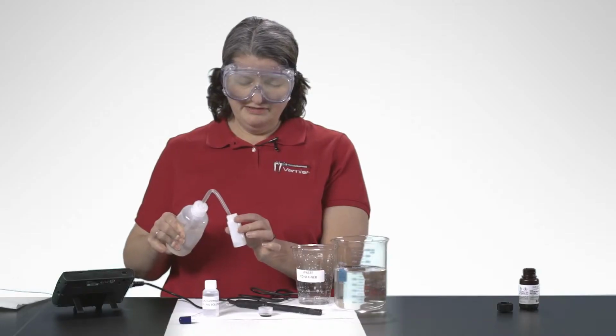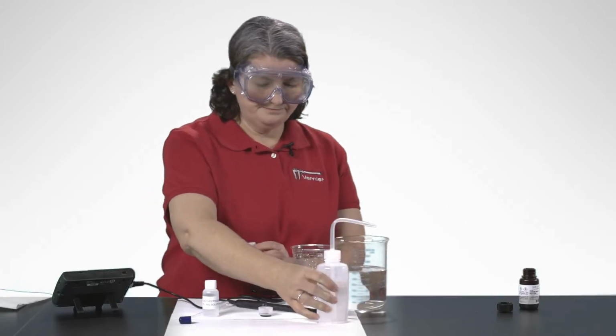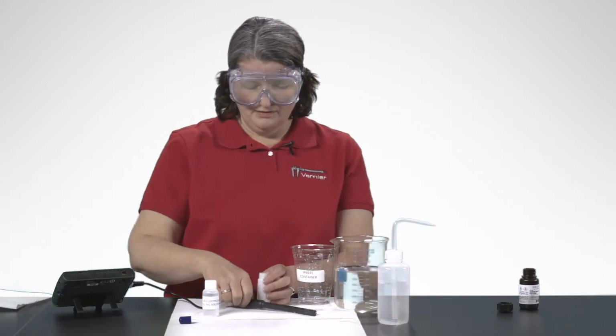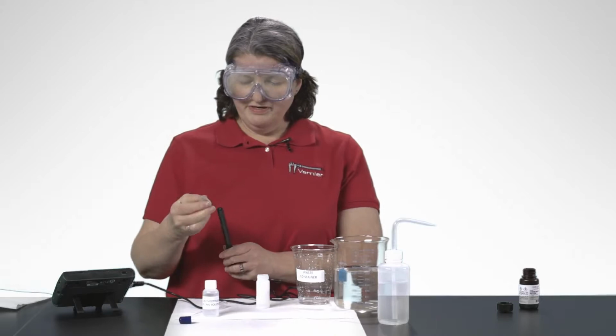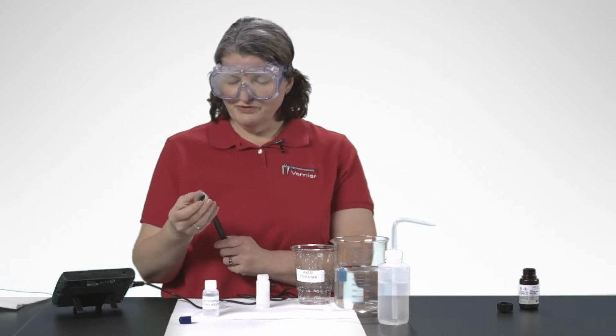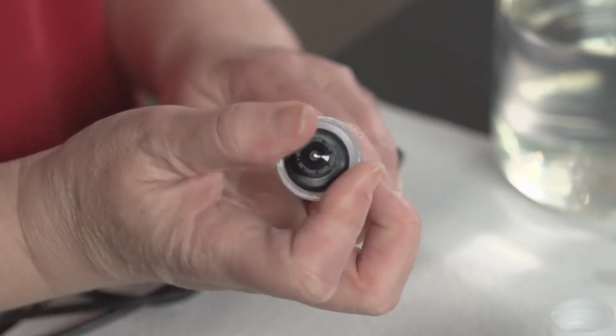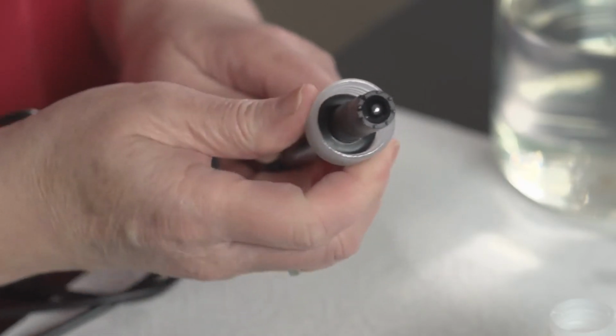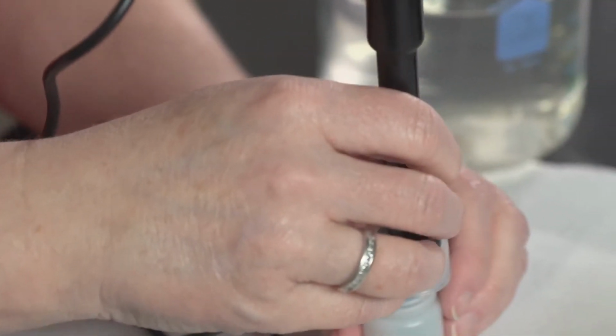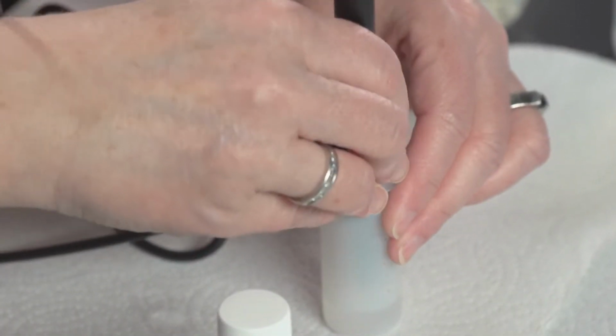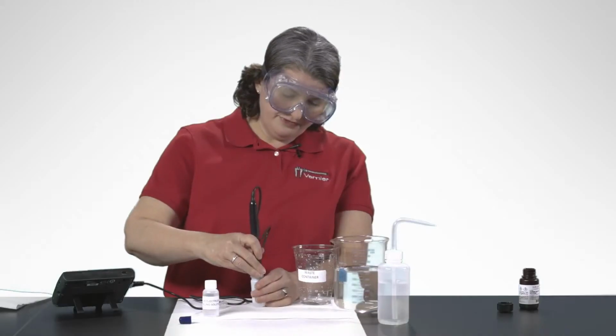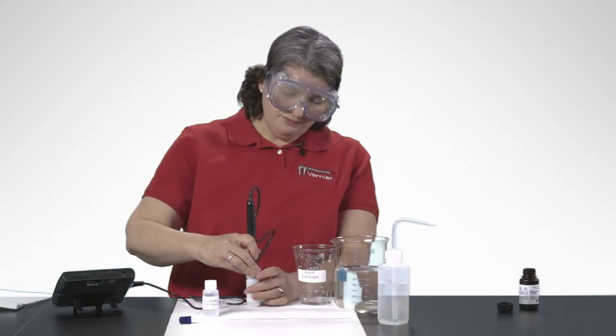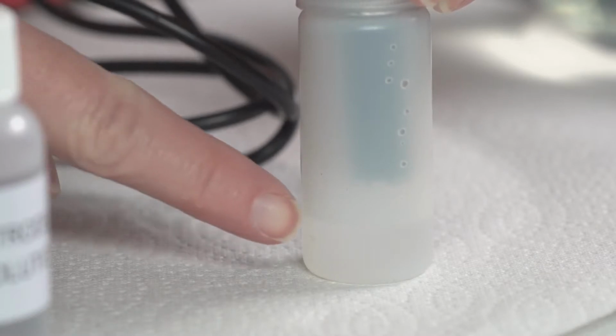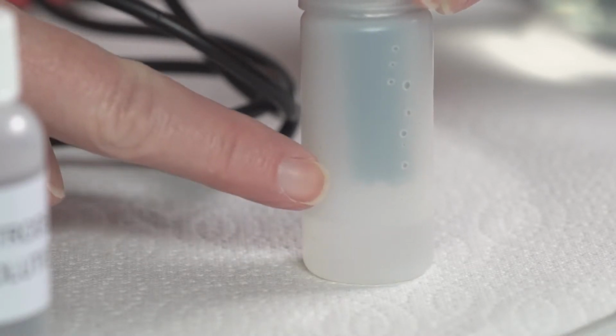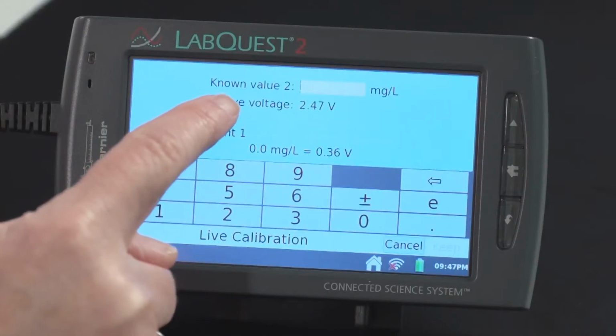We put a little distilled water in the bottom of this bottle. We're going to place the probe in this bottle, and this bottle comes with the probe as well. We slide the bottle's cap onto the sensor, put it in here. So what we're doing is we're creating a humid environment, 100% humidity, with the probe right over the top of that water, but not touching the water. And we watch our voltage again.